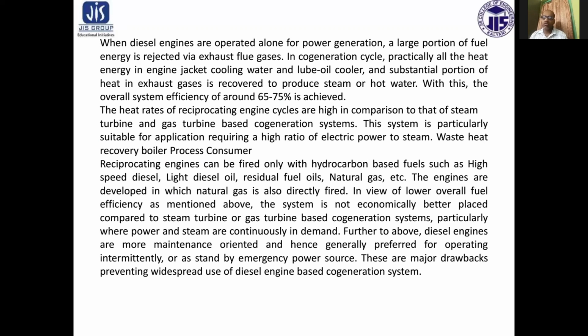In view of the lower overall fuel efficiency as mentioned above, this system is not economically better placed compared to the steam turbine or gas turbine based cogeneration system, particularly where power and steam are continuously in demand. Further, diesel engines are more maintenance oriented and hence generally preferred for intermittent operation or as a standby emergency power source. These are major drawbacks preventing widespread use of diesel engine based cogeneration systems.